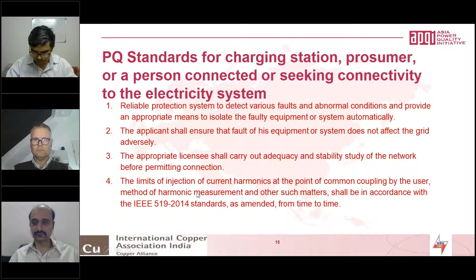Still some remaining part of the same standard, the connectivity standard. Measuring and metering of harmonics shall be a continuous process. So here is the emphasis on the continuous process. It's not that one time you measure and go away. So it has to be a continuous process, because harmonics may come at different times of the operation of the different types of equipment and the services, with power quality meters complying with the provisions of IEC 61000.